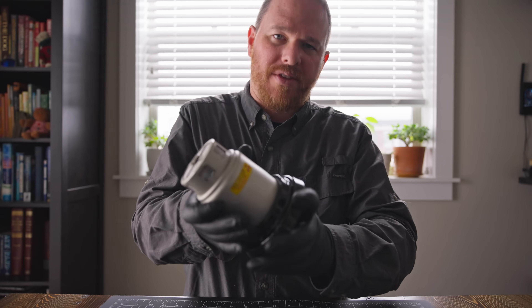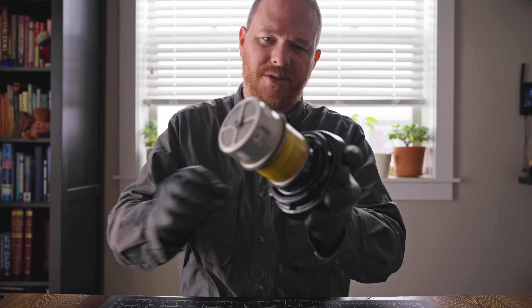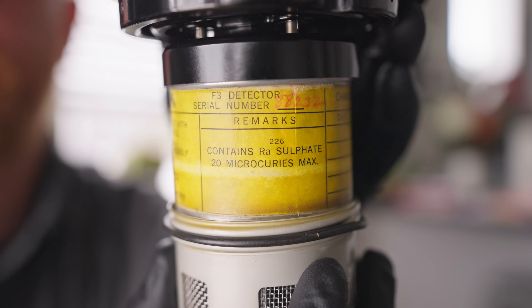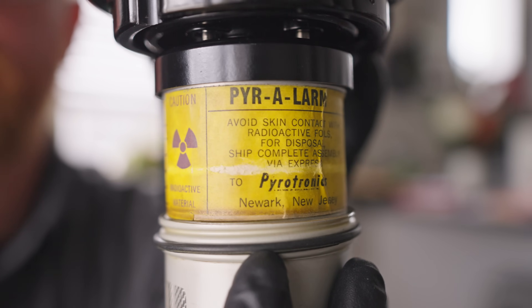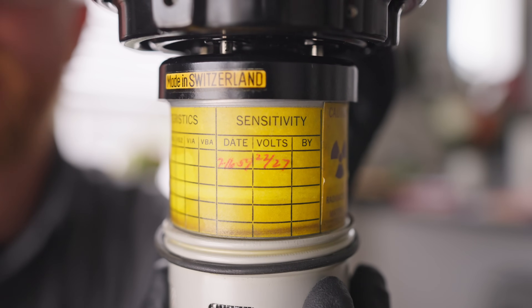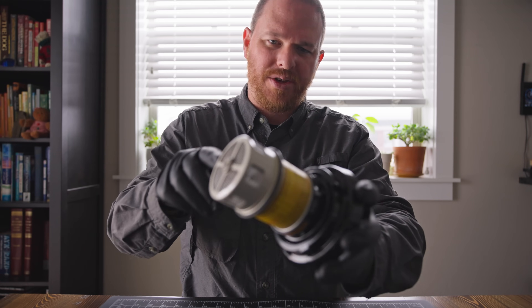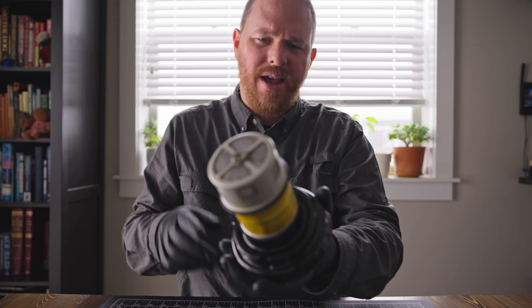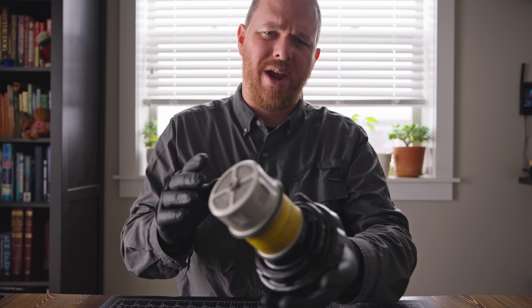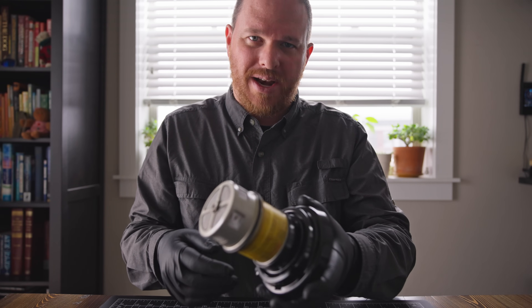The housing of this twists off and exposes a bit more information about this detector, like how much radium is used, a warning to avoid contact with radioactive foils, where to send it for disposal, and some servicing notes. The radioactive foil inside of here is where the radium is contained, and that was manufactured by the U.S. Radium Corp. under the trade name Ionotron foil.